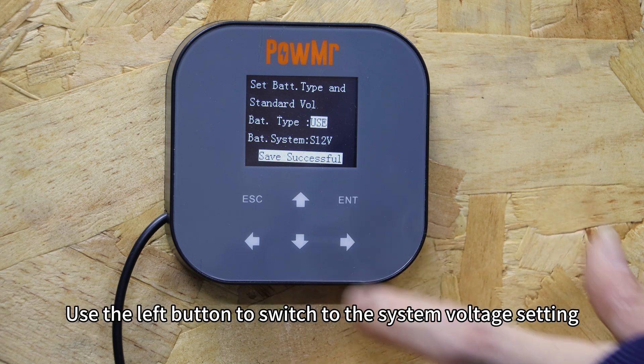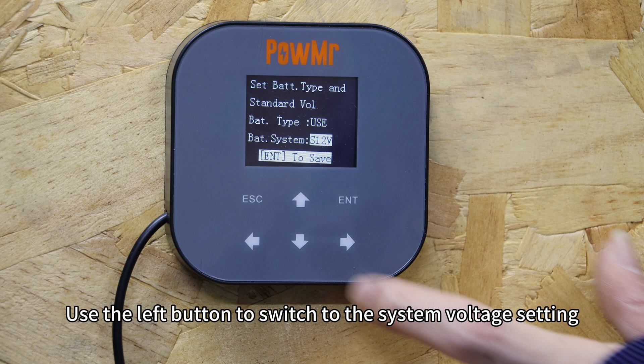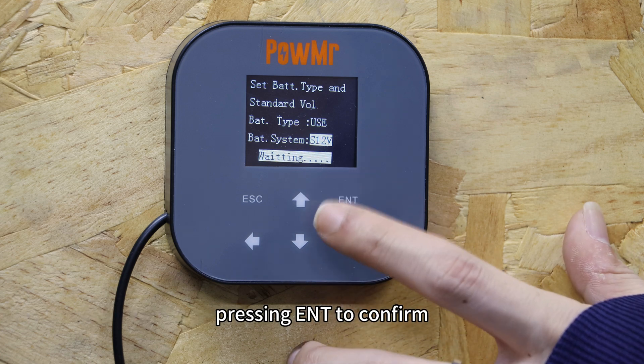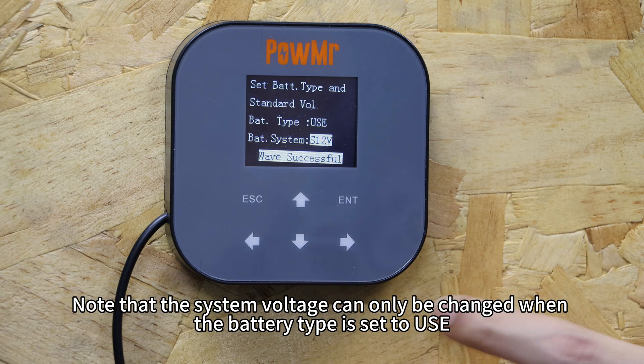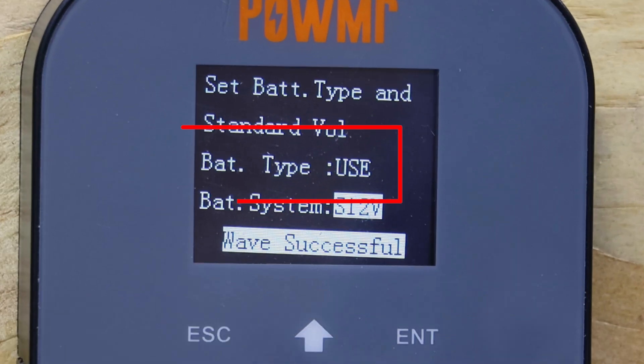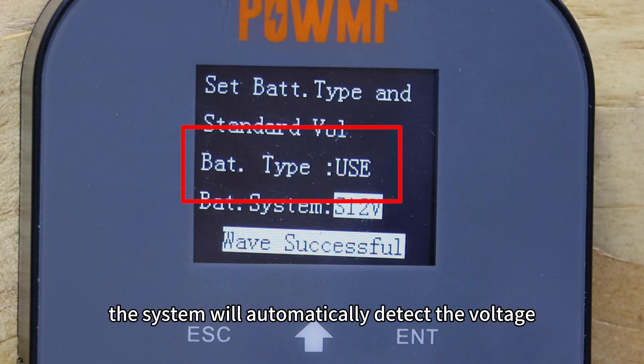Use the left button to switch to the system voltage setting and adjust the voltage using the up and down buttons, pressing enter to confirm. Note that system voltage can only be changed when the battery type is set to USE. For other battery types, the system will automatically detect the voltage.